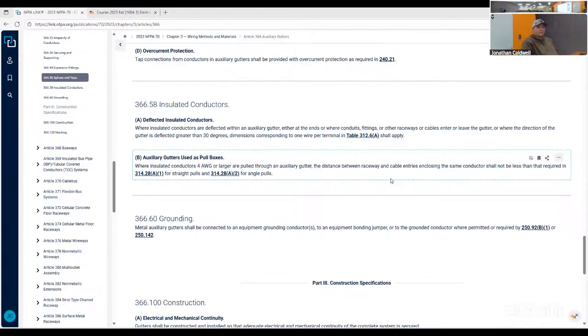I'll save you some time, save us all time. It's 6 and 8. So straight pulls is 8 times, and angle pulls is 6. At the end of the day, as long as you follow that, the 8 and 6, you're not going to have to worry about your bending radius on your wire, unless you're doing tray cable, and that's a whole different beast. But that's a super important one to remember. So let's try and remember just 8 and 6. If you can at least remember that, then you can just look up straight and angle and then you know which one's 8 and 6.